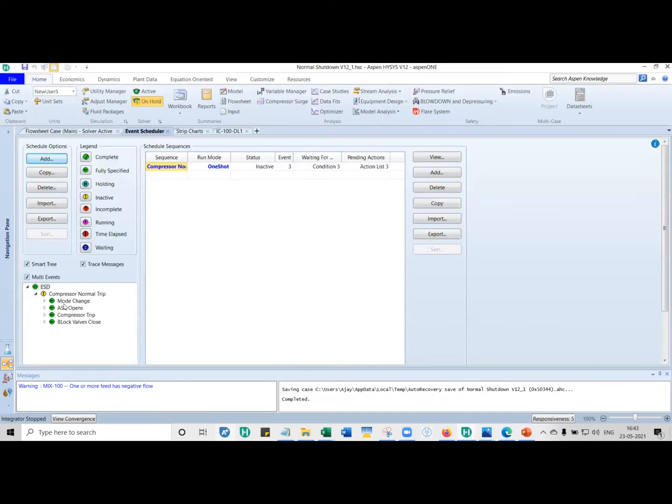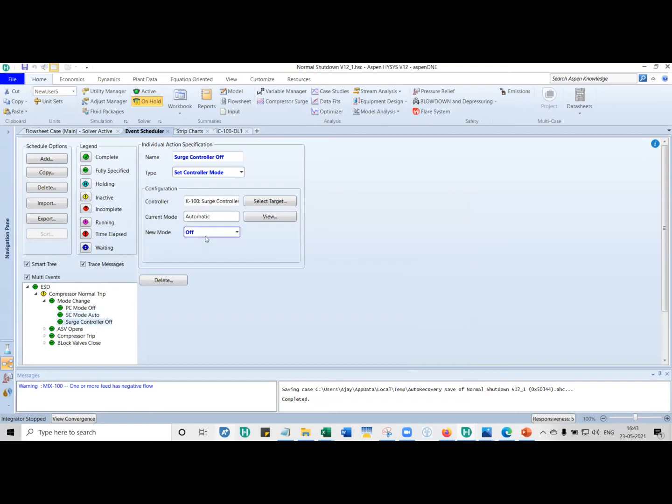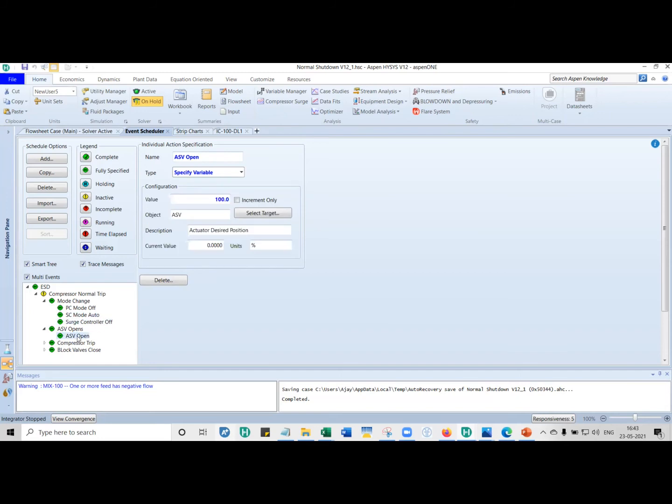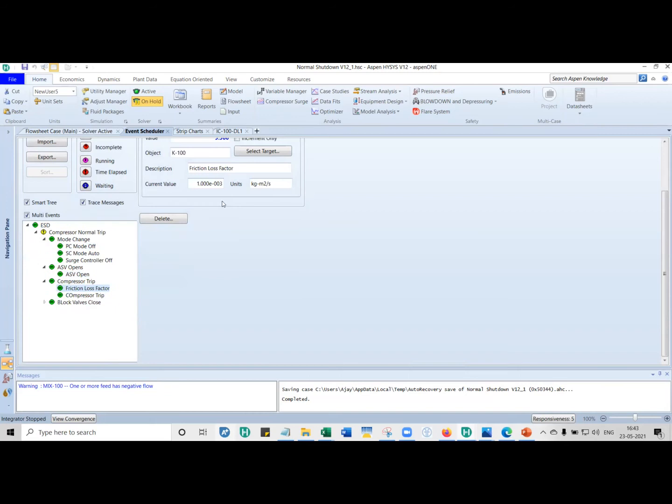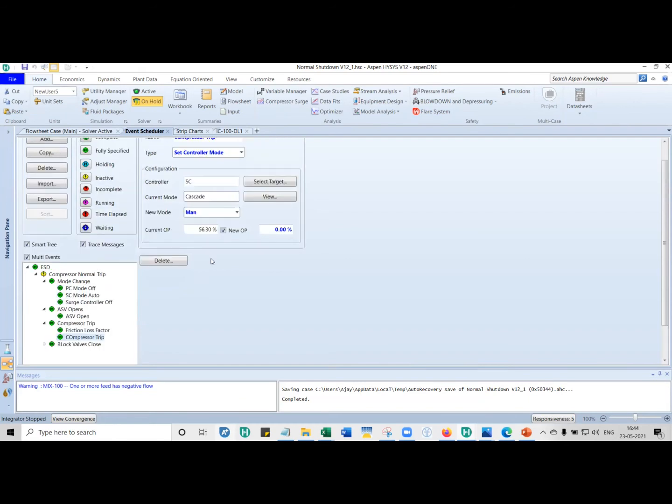The pressure controller from messing around with the compressor. We don't want any speed control when the compressor is coasting down. So taking all of this, what we do is mode change. First, the pressure controller, you switch it off. The speed controller, you change it to manual because I'm going to manually shut down the compressor. Then you shut down the surge controller also. Then the ASV opens. You say at what time you want the ASV to open. In this case, I said please open it 100%. And then you have to trip the compressor.